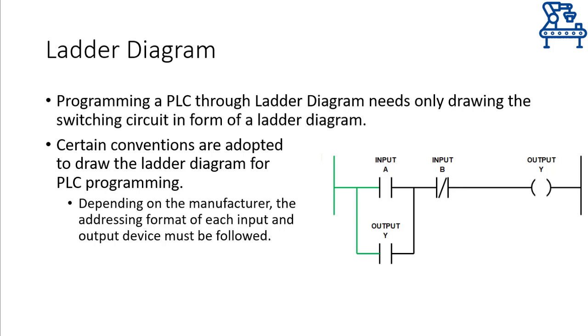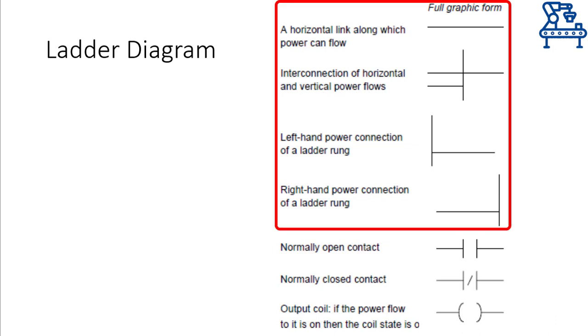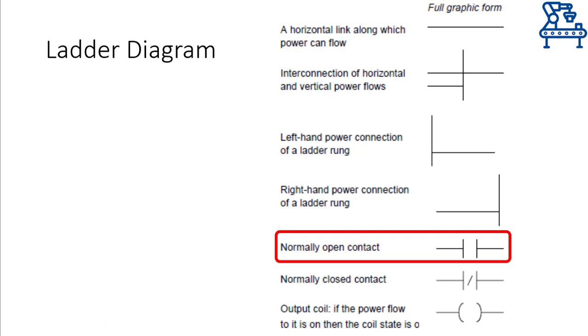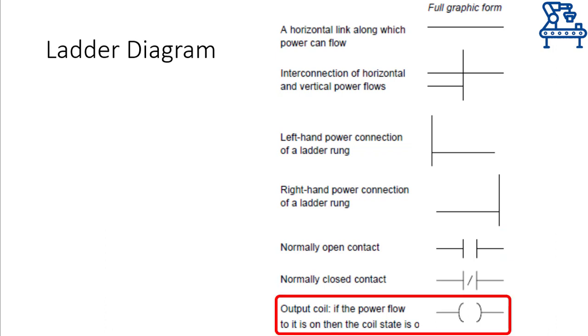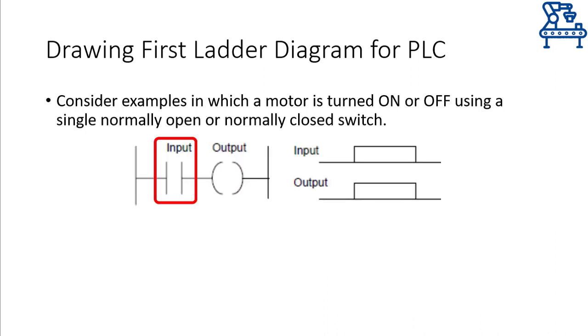Depending on the manufacturer, the suitable format for addressing input and output devices should be used. The standard symbols used in ladder diagrams include: lines representing power connections, a normally open contact symbol, a normally closed contact symbol, and an output coil symbol that may represent any connected output — whether an LED, a motor, or another actuator. If you want to turn on a motor through a single normally open switch, the switch is connected in series with the output coil. When pressed, power flows through the coil turning it on; when released, the output is de-energized. With a normally closed switch instead, the output coil is energized when the switch is not pressed and turns off when the switch is pressed.